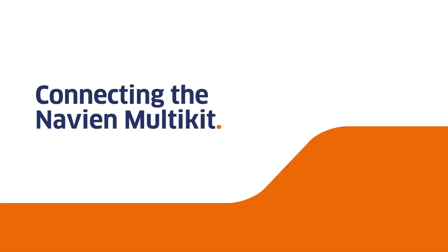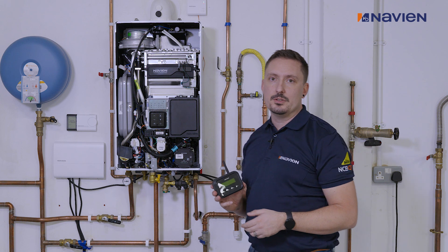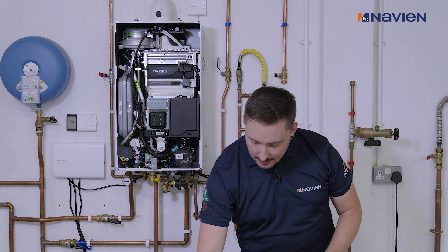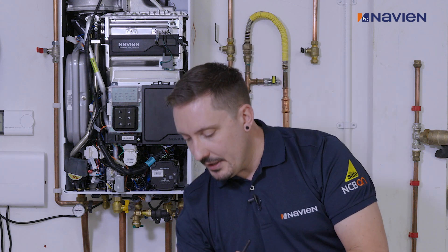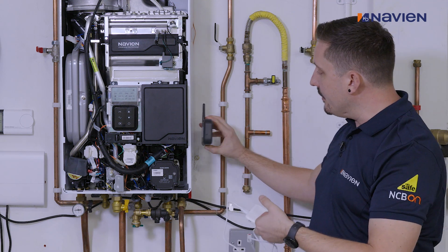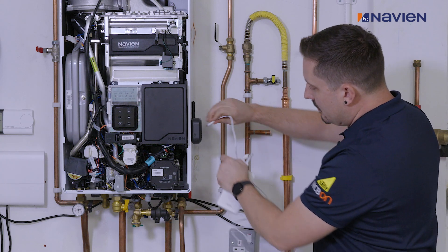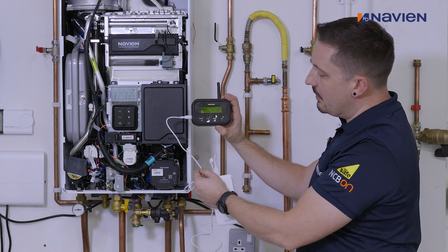Now I'd like to take you through opening up the cover and getting into the unit. Here I have the Navien Multikit and I'm going to be connecting it to our NCB 500 combi boiler. In this scenario I'll be required to use the white connection cable, which will be connecting to the front of the display. First off I'll be connecting up the power cable, which is a USB-C type. Popping that on the side - connect that up, and as you'll see, the power is up and display is on.